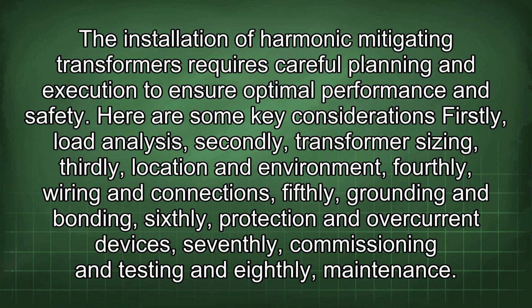The installation of harmonic mitigating transformers requires careful planning and execution to ensure optimal performance and safety. Here are some key considerations. Firstly, load analysis. Secondly, transformer sizing. Thirdly, location and environment. Fourthly, wiring and connections. Fifthly, grounding and bonding. Sixthly, protection and overcurrent devices. Seventhly, commissioning and testing. And eighthly, maintenance.